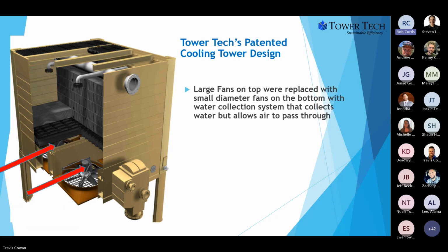And one of those areas was, if you think about cooling towers in general, where are the fans located? Most of the time, they were located on the top of the cooling tower. We could go into the history of cooling towers and talk about how the first cooling tower had fans at the bottom, but then in the 40s and 50s they moved them to the top. Well, we replaced that with small diameter fans located on the bottom of the cooling tower by incorporating a water collection system. We patented that water collection system. It has tremendous benefits. And because of that one change, man, there's been a whole array of benefits that took place.